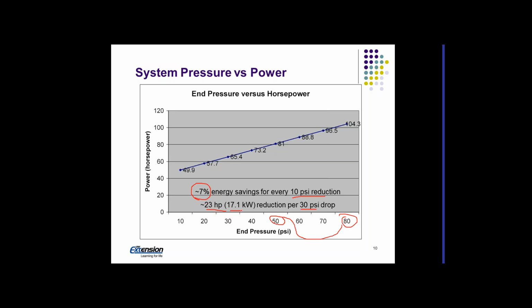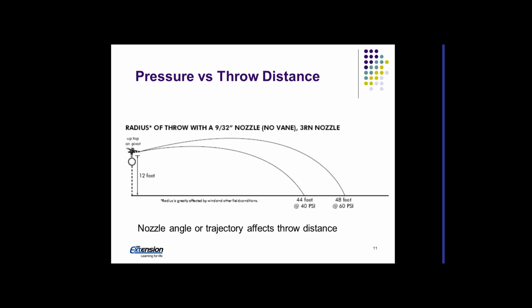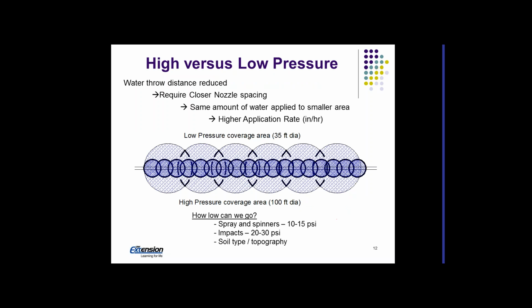So that's a saving that will translate into energy savings, and we'll show you how in a minute. When we reduce the pressure, that reduces the throw distance. This is an illustration. If we've got a radius of throw of 48 feet with 60 psi, reduce it to 40 psi, that changes to 44 feet. That may not be much for this particular example, but it can be, depending on the type of nozzle package or sprinkler package you choose.